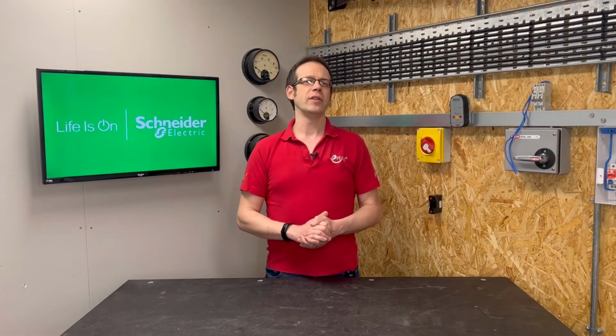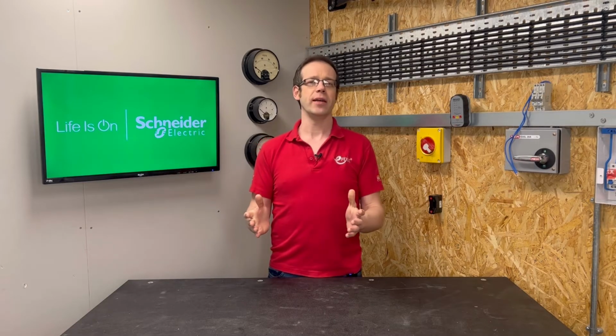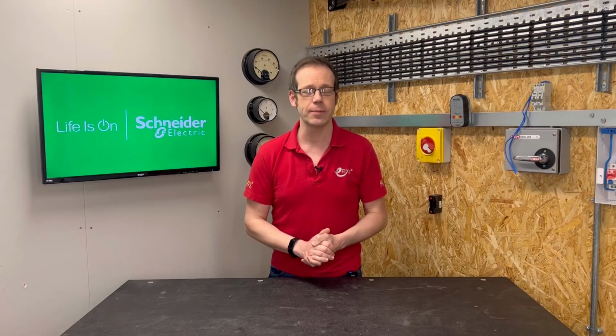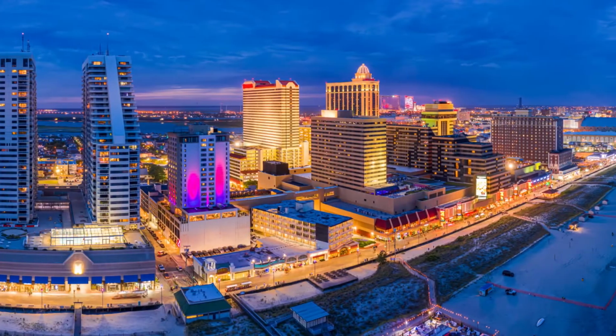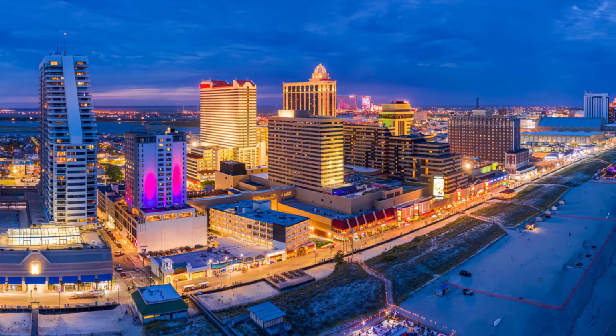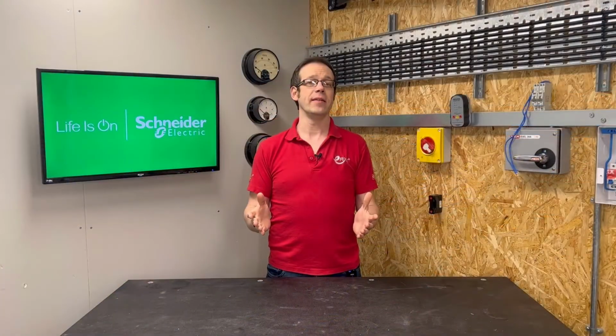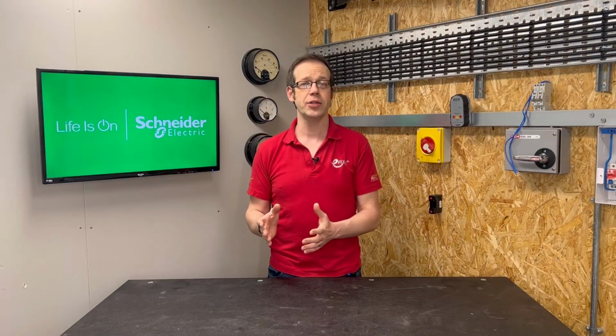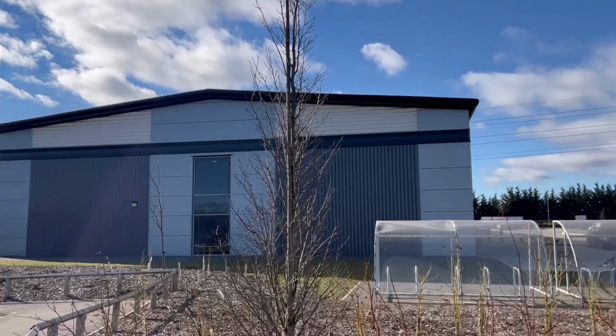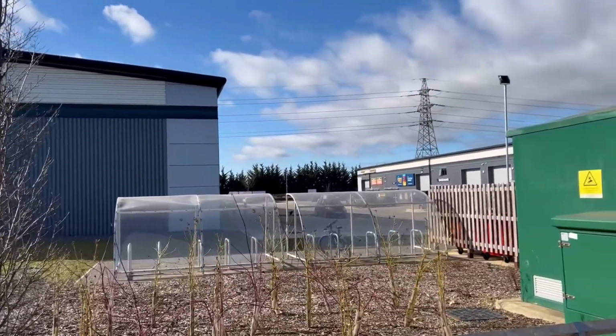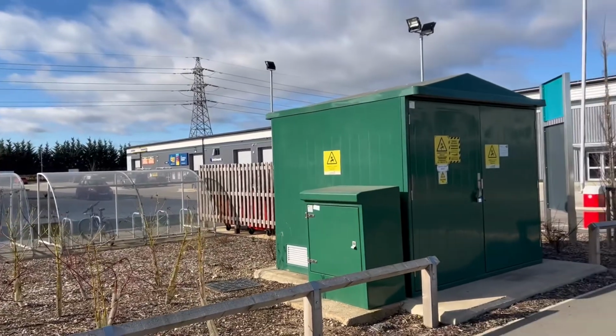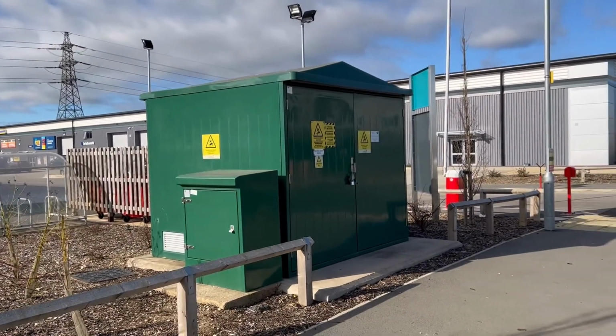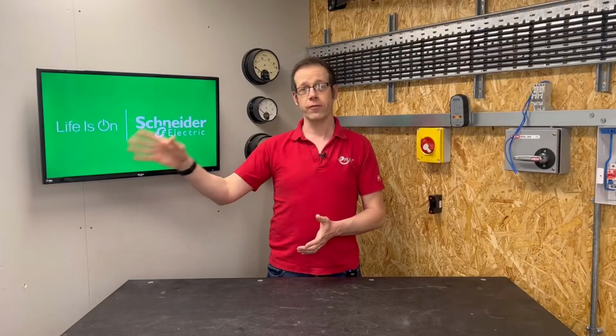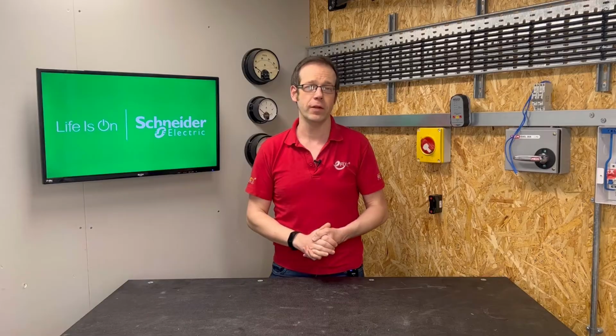Why then would we need devices rated higher than the 6 kA most circuit breakers are rated at? Well, as I mentioned earlier, Guidance Note 3 talks about single-phase supplies up to 100 amps and also talks about not being in a city centre. In either of these cases, other factors must be considered. If we look at industrial and commercial installations, many premises have an 11 kV or 33 kV supply to a transformer right outside. The earth fault loop impedance in these cases will be extremely low as there is so little cable between the transformer and the consumer's intake position that very high currents may flow when a fault occurs.